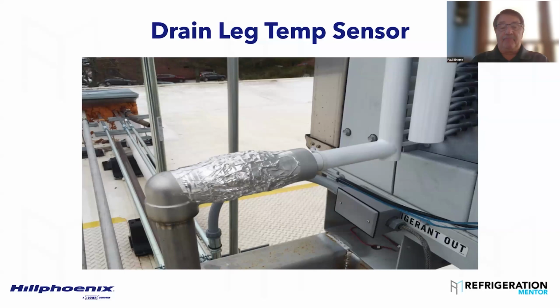This one here? I brought this one up because this is a good example of an okay installation. What I like to see is we want to be within 6 to 12 inches of the header, and we want to have 1.5 inches of insulation with a white PVC wrap around it. This is okay, but still it's not enough insulation, and the sun will heat it up even though it's a reflective surface. We want to keep the moisture off of it.